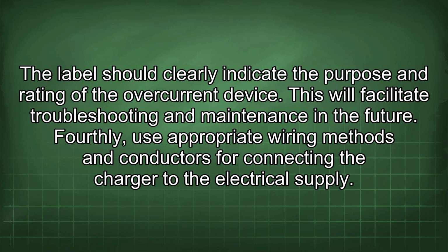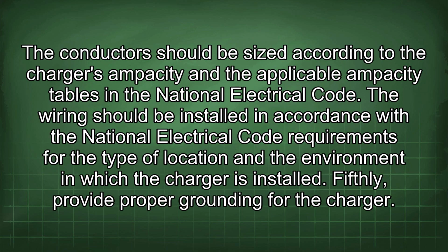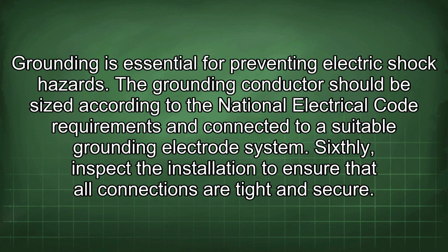Fourthly, use appropriate wiring methods and conductors for connecting the charger to the electrical supply. The conductors should be sized according to the charger's ampacity and the applicable ampacity tables in the National Electrical Code. The wiring should be installed in accordance with the National Electrical Code requirements for the type of location and the environment in which the charger is installed. Fifthly, provide proper grounding for the charger. Grounding is essential for preventing electric shock hazards. The grounding conductor should be sized according to the National Electrical Code requirements and connected to a suitable grounding electrode system.